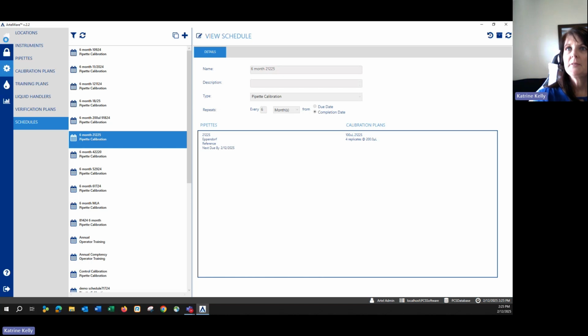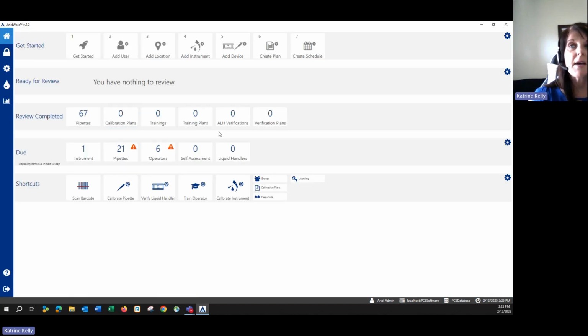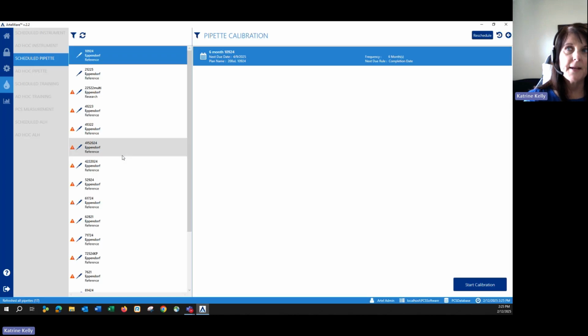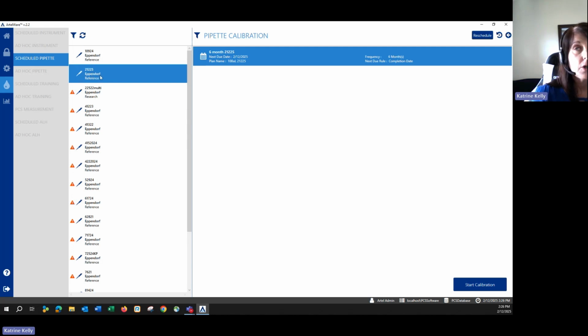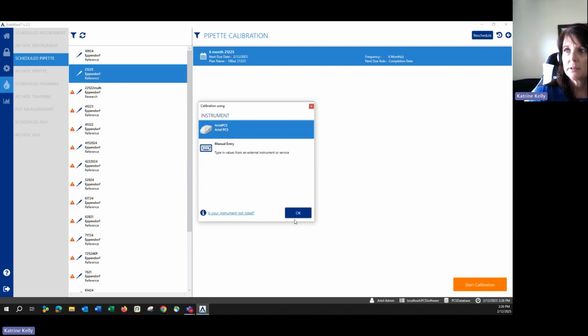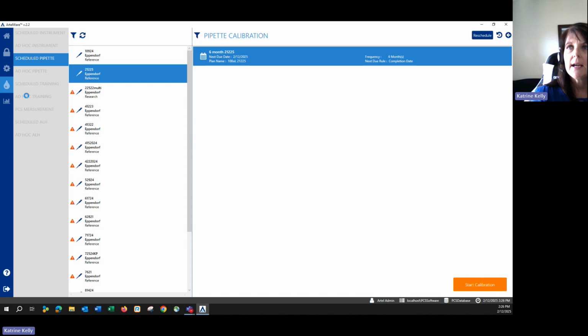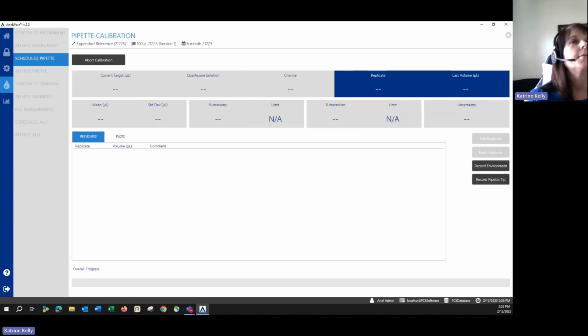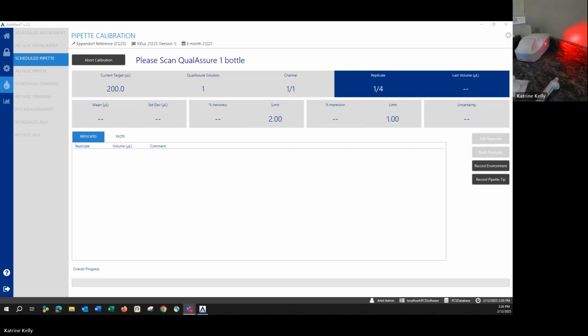Okay, so now all my inventory is entered in. At this time, I can start performing my calibrations. So I'm going to click on my due bar for my pipette that's due. So I have 21 pipettes that are due. There's the pipette that I just entered in. To start the calibration, I just select the pipette and click Start Calibration and select Artel PCS and click OK. Now at this time, I'm going to change my camera over so that you can see the PCS instrument. All right, so you should see the PCS instrument on the counter and the barcode scanner is lit up on the side here. So it does have an integrated barcode scanner.